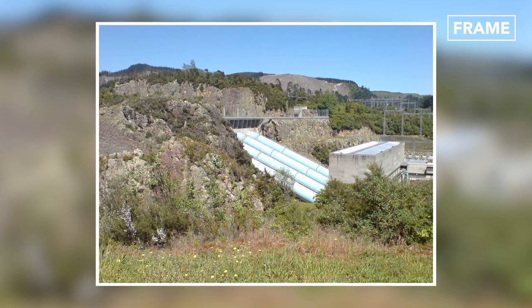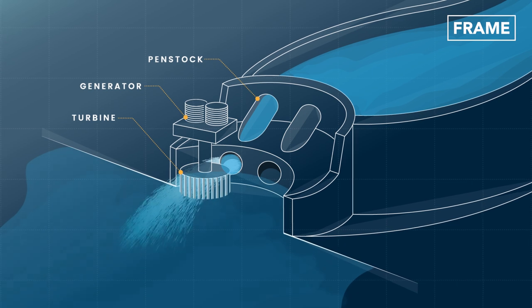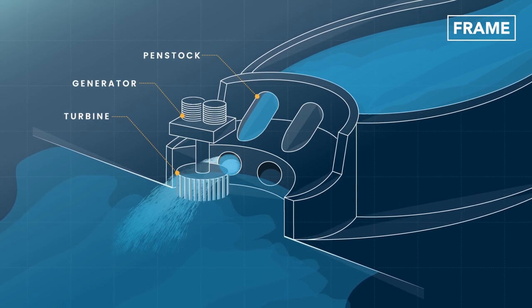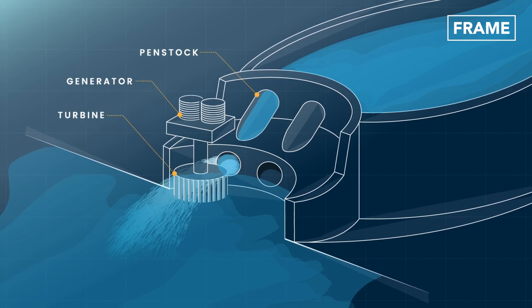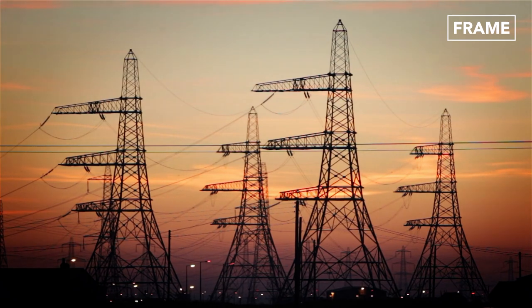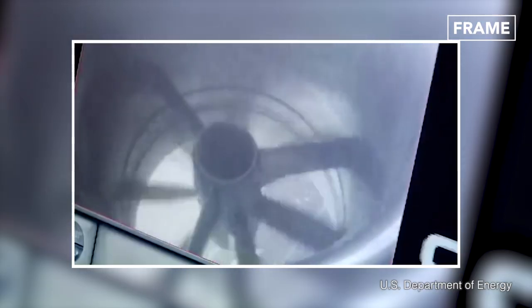Water is released from the reservoir via the penstock. These are channels that control the slope of the falling water to maximize the working efficiency of the dam. The moving water from the penstocks drives turbine blades, spinning the turbine shaft that leads into the generators that use the powerful rotation to generate electricity. The amount of electricity that can be generated is determined by the depth of the intake under the reservoir's water surface and the rate at which the water flows through the turbines.